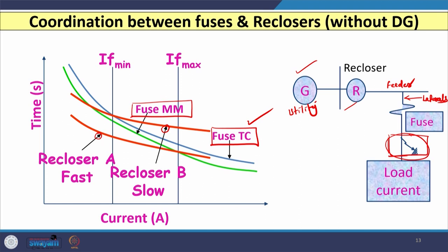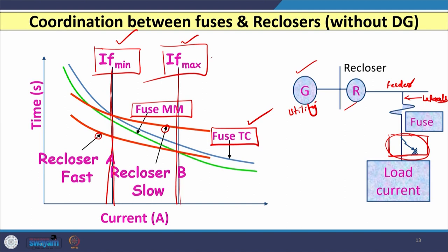You can see that I have considered here two vertical bars, one is the minimum fault current and another is the maximum fault current. So, we have to coordinate this recloser and fuse characteristic between this minimum current and maximum current. Minimum current is decided by the feeder's or lateral's full load current. What maximum full load current the lateral or feeder can withstand with a percentage of overload, that is my IF min. Above that, whatever current I consider is the minimum fault current it can detect. And there is also a maximum fault current which is detected by this recloser and fuse depending upon the capacity.